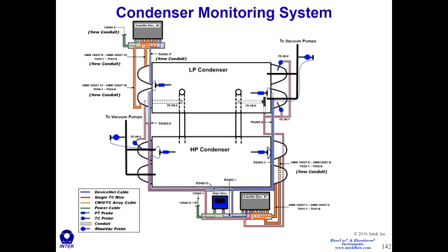We have test grade temperature sensors, both on the outlet, the turnaround. So the cooling water comes in this direction, turns around and enters the HP condenser. We have RheoVacs or PTs monitoring both the hot and cold end of each shell. We have RheoVacs monitoring the vacuum pump capacity out here. And we have water box instrumentation here and here monitoring the performance profiles.